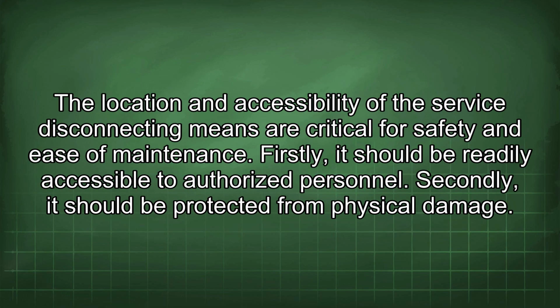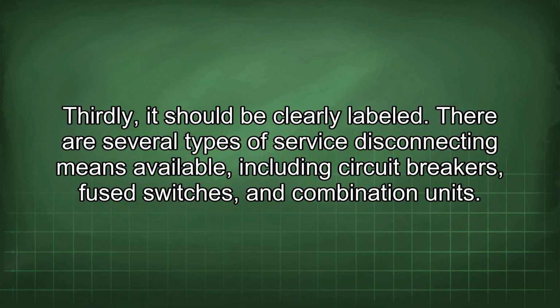The location and accessibility of the service disconnecting means are critical for safety and ease of maintenance. Firstly, it should be readily accessible to authorized personnel. Secondly, it should be protected from physical damage. Thirdly, it should be clearly labeled. There are several types of service disconnecting means available, including circuit breakers, fuse switches, and combination units.